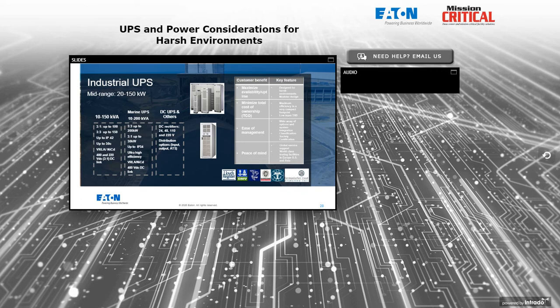Another thing we want to be careful about when specifying marine UPS is how the grounding is to be done. In some shipboard applications, the ship's hull is not intended to be used for grounding for power infrastructure. So how would the UPS's input and output be grounded for safety and for safe servicing and for isolation of things like communication cards and that type of thing needs to be considered at the time of the specification for the UPS.